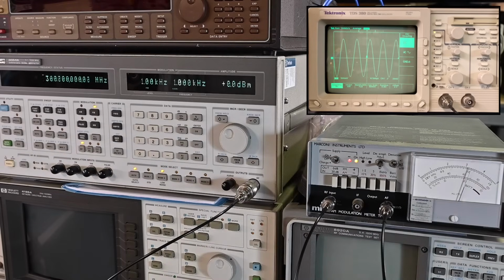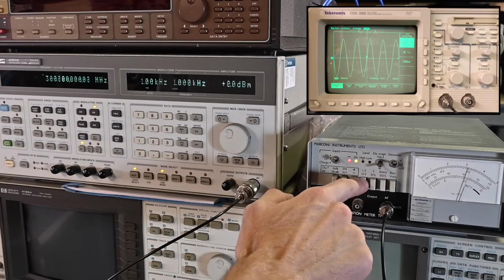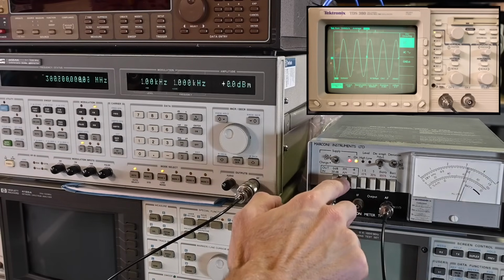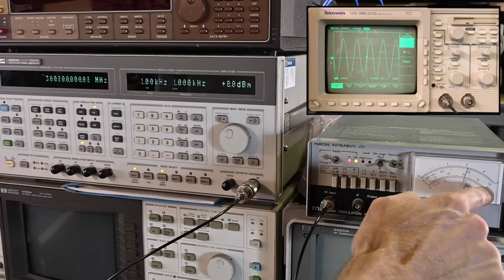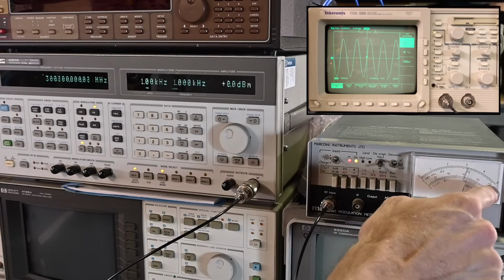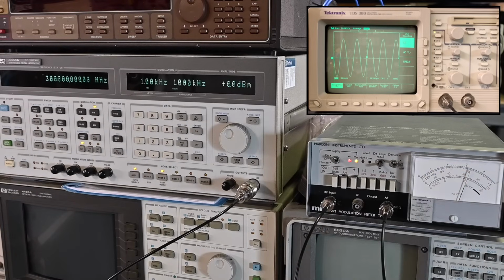All right, so this is on 1.5 kilohertz full scale in the FM mode. That's the second scale down. So 1.5 kilohertz full scale deviation. We're on 1 kilohertz and it's reading very, very close to the 1 kilohertz tick mark. So no problems. That range is working correctly.